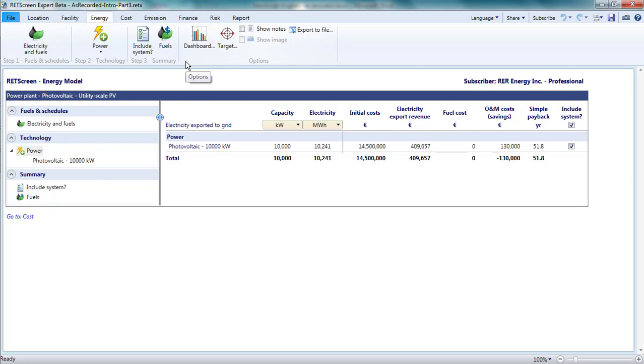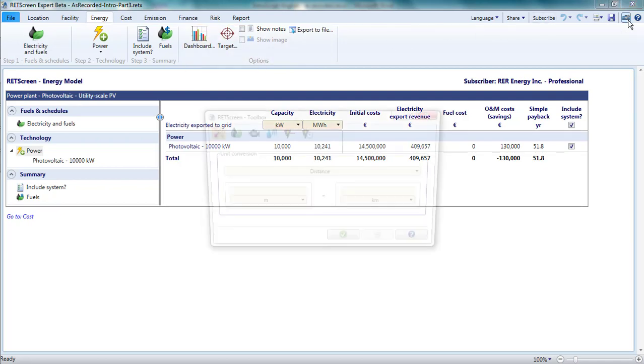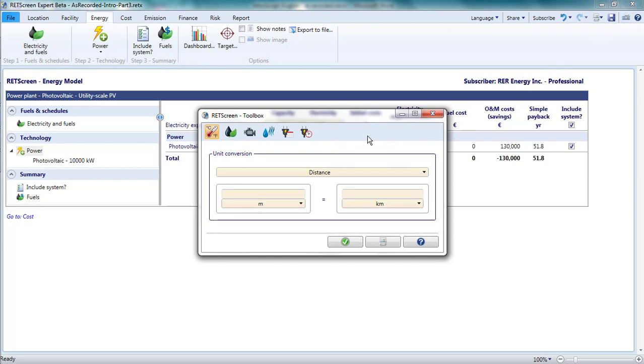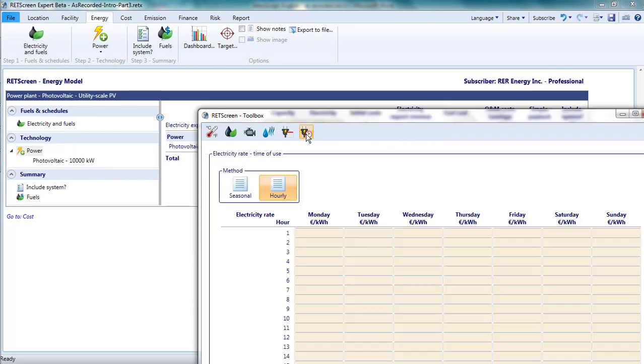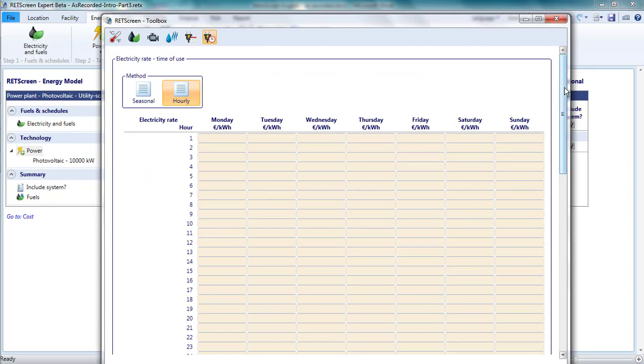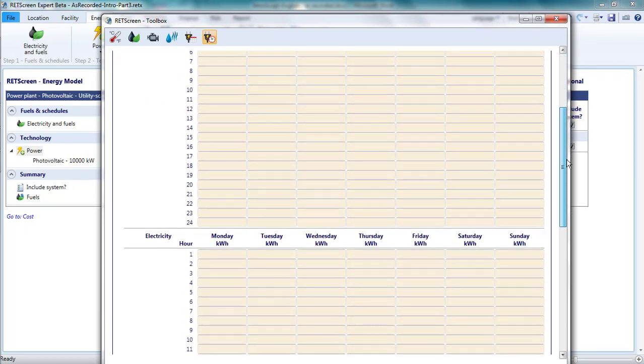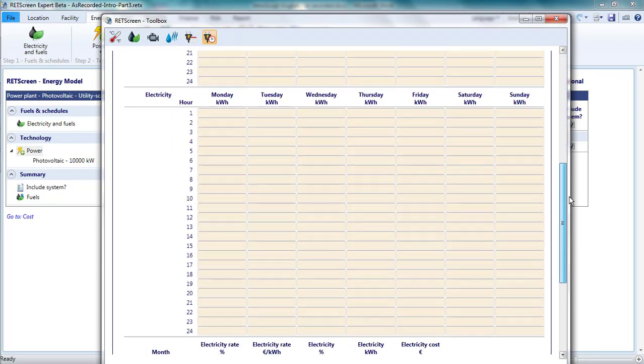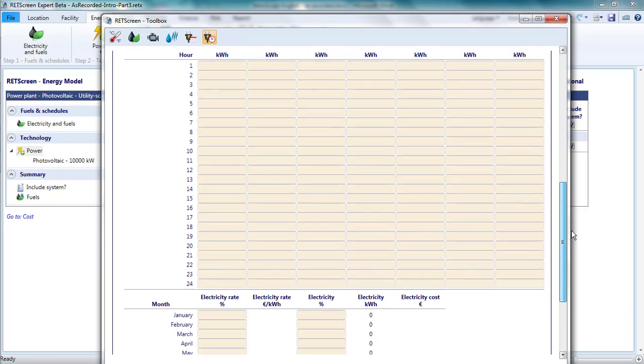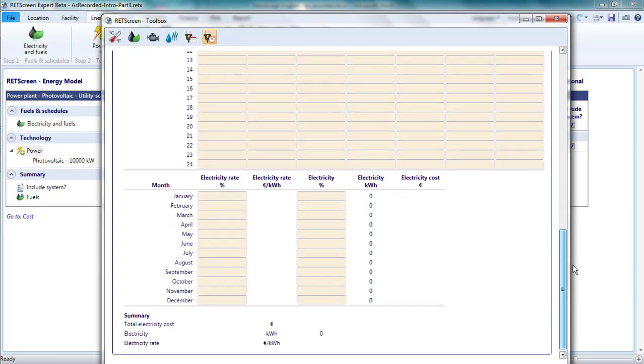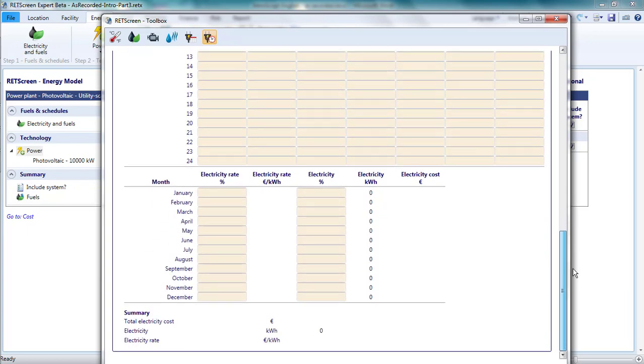If the tariff varies by time of day or by day of the week, RETScreen includes a tool that may assist in determining the annual average per kilowatt hour price earned for electricity sales. Opening the toolbox and selecting the electricity rate time of use tool, you can enter the price of electricity for each hour of each day of the week. Then, you estimate production for each hour using a typical profile over the course of the day. This requires some careful thought and judgment, but you may still find it useful.